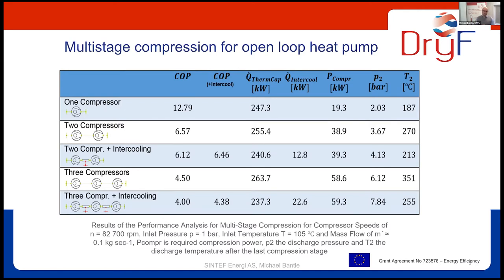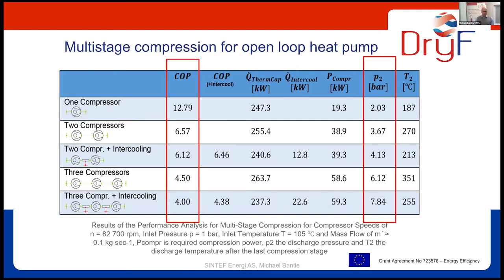If we are designing our open loop heat pump, we have the choice to work with different refrigeration compressor stages. If we would just choose one compressor stage and a relatively low pressure increase, one compressor would give us around 2 bar at the outlet. That would mean we could reheat up to 120 degrees. Then we would need a very large dryer system, which can operate at very low delta T. On the other hand, we have a three- or multi-stage compression system, which can lift to higher pressure levels, where we can recondense between seven and eight bar, which would give us almost 170 degrees temperature, but the efficiency would go down. So one of the main tasks we were doing here was to find the sweet spot between the right dryer size and an efficient heat pump system, and how many compression stages we need.